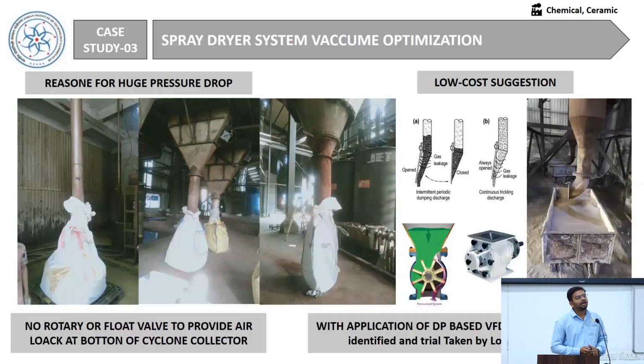So these are the images. These are very critical cases for ETP plants as well as ceramic and chemical plants, because not maintaining the vacuum in the spray dryer also affects the HAG system, which is like a boiler. In a boiler, we need to maintain some negative draft. If we do not maintain it, it will pressurize the boiler walls, and it can damage the boiler walls as well as the hot air ducting. So managing the vacuum is very crucial, because a normal plastic bag cannot manage the vacuum.